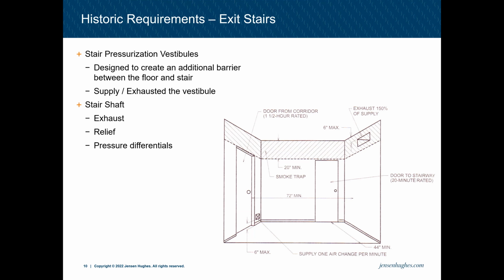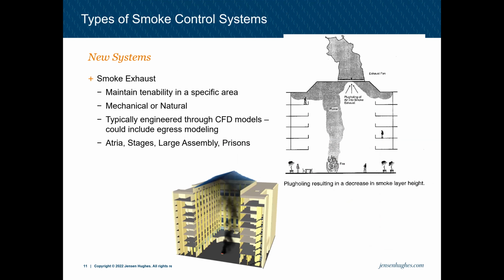And then there are different performance criteria in terms of pressure differentials. With vestibules, we'll hear a term of inches of water. So it'd be 0.1, that's the measurement of pressure used for these systems. Today's requirements are between 0.1 and 0.35 inches of water. Older systems had just a minimum of 0.1. Some had a minimum of 0.15, and those numbers have changed throughout the years based on different research of how much pressure is actually required to keep out smoke. So that was pretty much stair and elevator pressurization.